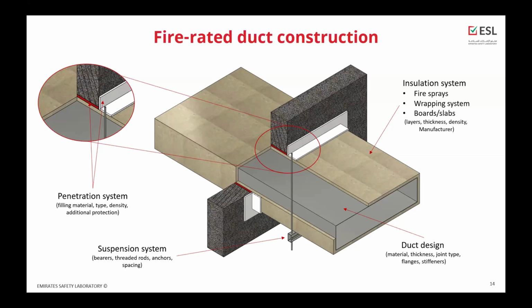The next thing is the suspension system, which covers, for example, bearers, thread rods, anchors, and spacing. And one of the most important parts, which some companies are forgetting about, is the penetration system: how your duct must be sealed when it's passing through the fire division, and this belongs to that system.